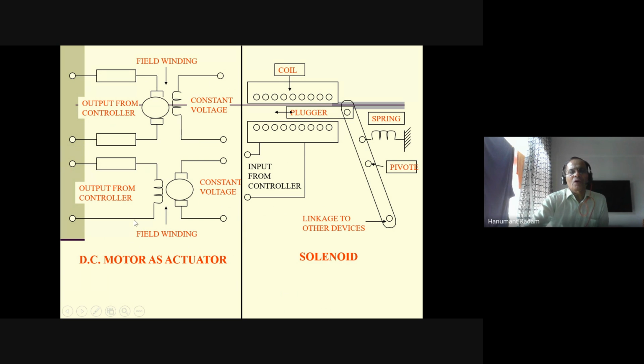So this is what a field winding is. This is a field winding: output from the controller, and a constant voltage. You get field winding, and this constant voltage goes through this solenoid valve: plunger, spring, and the input from the controller here. This is a coil and plunger, which means this is how a solenoid functions. Through the solenoid the piston is moving, and the piston position is linked to the valve. So this type of mechanism is there in electric type actuators.